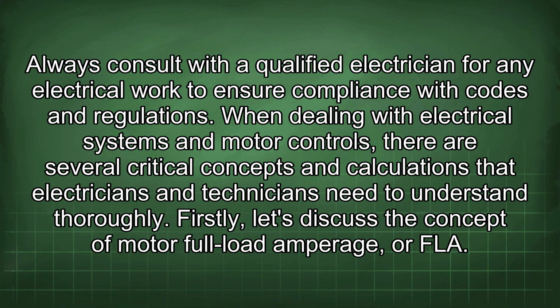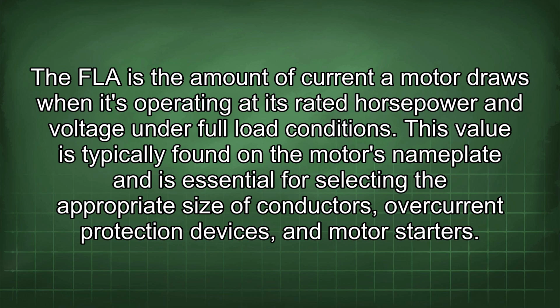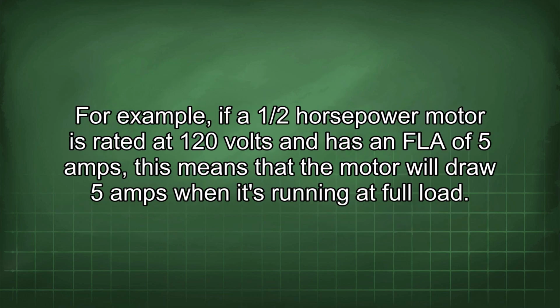When dealing with electrical systems and motor controls, there are several critical concepts and calculations that electricians and technicians need to understand thoroughly. Firstly, let's discuss the concept of motor full load amperage, or FLA. The FLA is the amount of current a motor draws when it's operating at its rated horsepower and voltage under full load conditions. This value is typically found in the motor's nameplate and is essential for selecting the appropriate size of conductors, overcurrent protection devices, and motor starters. For example, if a 1/2 horsepower motor is rated at 120 volts and has an FLA of 5 amps, this means that the motor will draw 5 amps when it's running at full load.